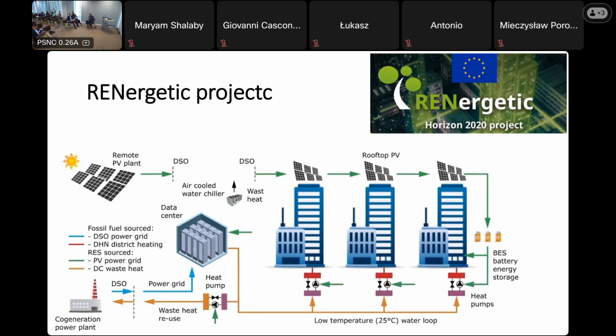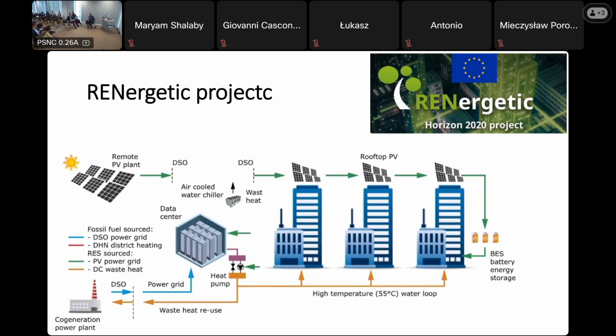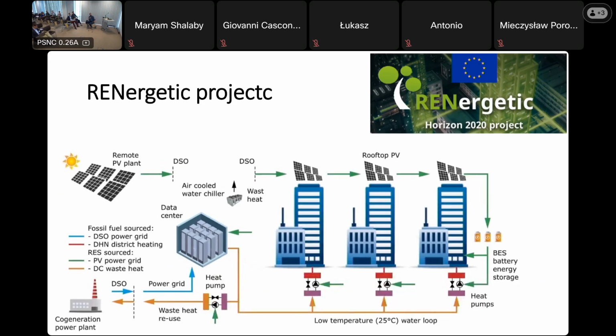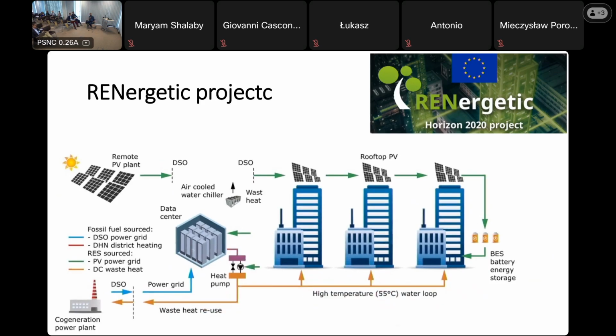Another possibility is to create a low temperature loop for district or campus heating, here at 55 and 25 degrees Celsius. The heat pumps are located at each building and provide a dedicated temperature for each building according to its heating curve, assuming this is enough to keep the building supplied with enough energy and temperature on the heating curve.